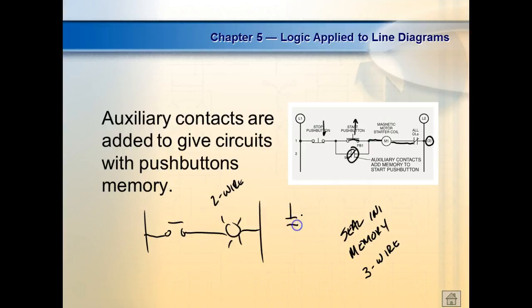Out here in the power circuit, I'm not going to draw the overloads or sensors. Out here I'd have the power contacts. This might be L1, labeled L1, and down here labeled T1. Up here this would be L2, down here T2. Up here this would be L3, down here T3. But the name of the contacts would be M1 — these are your manufacturer numbers.